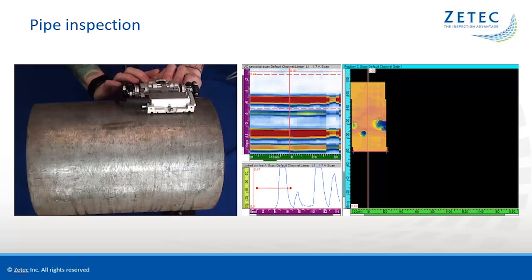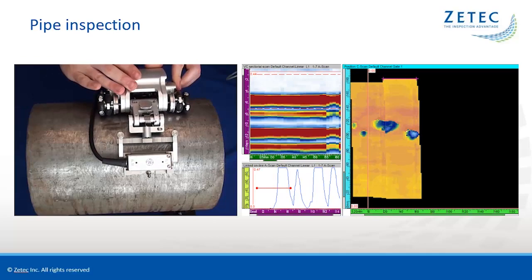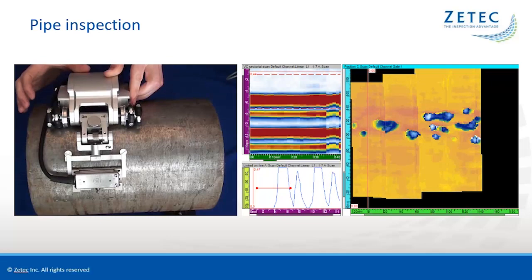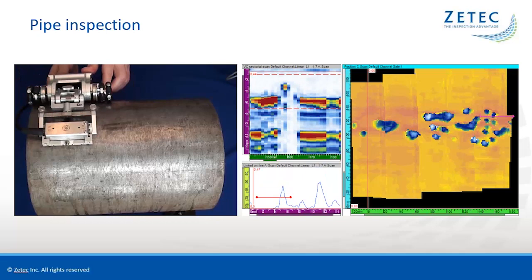As the Sweeper is moved, the probe position dynamically updates on the C-scan, filling the view with thickness information for the area scanned. Using Zetec's dedicated corrosion mapping probe, the active aperture is 1.6 inches wide, which makes for a very rapid scan of the pipe. This technique offers a considerable time gain when compared to the traditional thickness gauge or conventional UT probes on a grid.